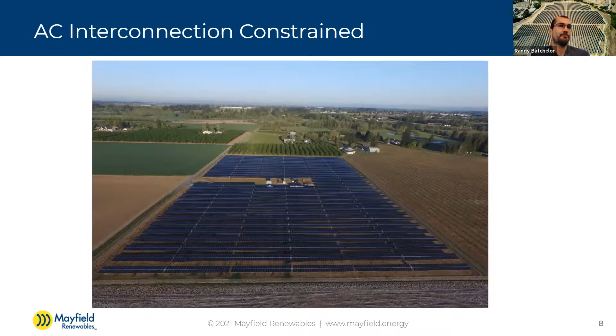And if you're AC limited, you just push right up against the limits of the inverter if you still have space. So a lot of systems now we're seeing going in at 1.5, right up at the limits of what the inverter can handle for loading ratios.